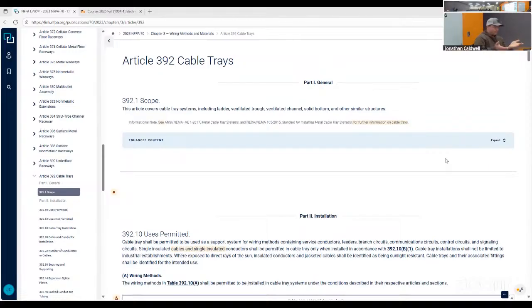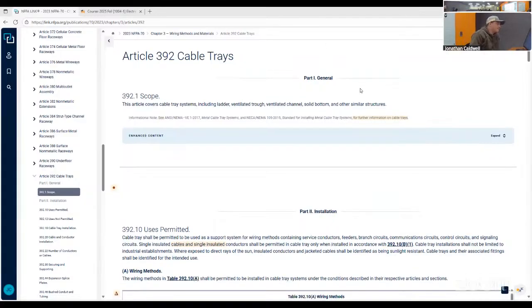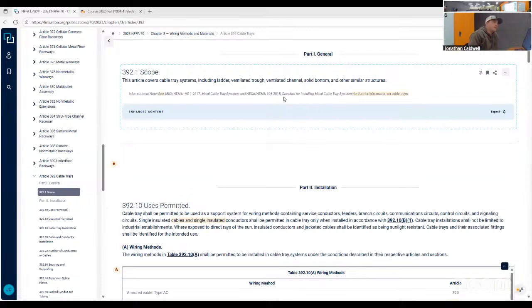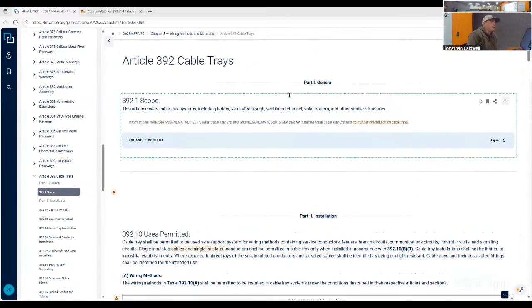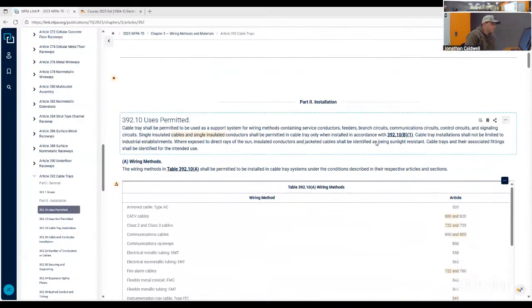So the hard part about cable tray is mostly what is the fill, and then how do you ground it? Obviously, if it's not metal, don't ground it. That's simple. The fiberglass cable tray that we work with, we don't ground it, but we ground the structure around it. That makes sense, because once you get a bunch of big cables in the cable tray, it gets kind of heavy, so you end up having to ground the steel structure. And with basket tray, technically you're supposed to ground it. They do make fittings and all sorts of stuff for that, for basket tray.